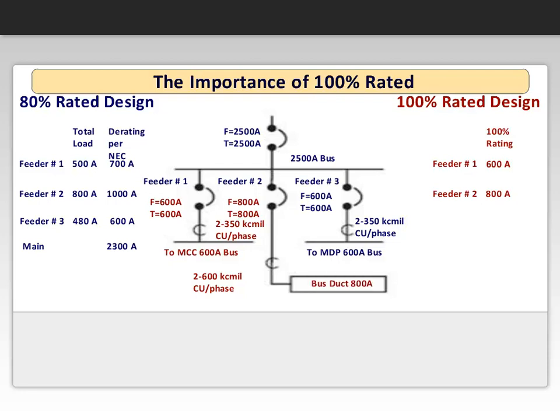at 800 amps. Feeder number 3 remains 600 amps, and the breaker and cable size remain the same. Now the main breaker can be sized for 2000 amps instead of 2500 amps. This is a tremendous savings and results in reduced cost for breakers, cable, and bus.